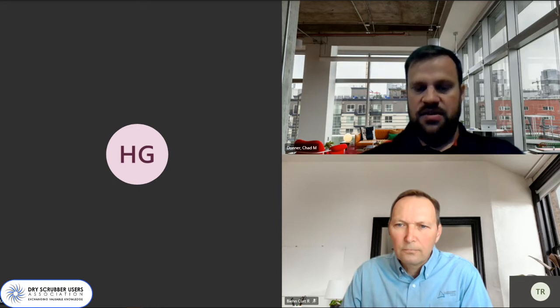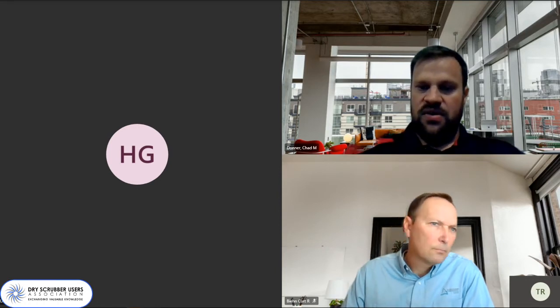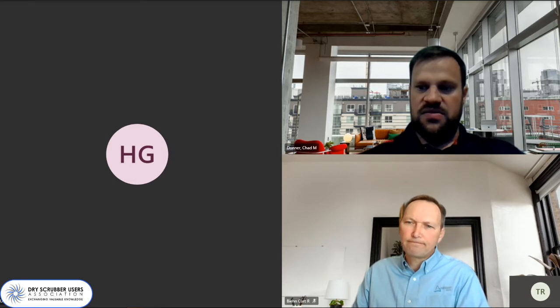Another area that we focus on: the silos are all prefabricated and sized to ship on the road, so they're limited in their overall outside dimension or diameter. Those areas are usually pretty cramped, and there's a lot of hydrated lime potential in those cramped quarters. So trying to take as much risk out of the silo skirt as possible by piping vents outside, and looking at those expansion joints to improve their reliability and minimize leak potential inside the silo skirt, is a big one.